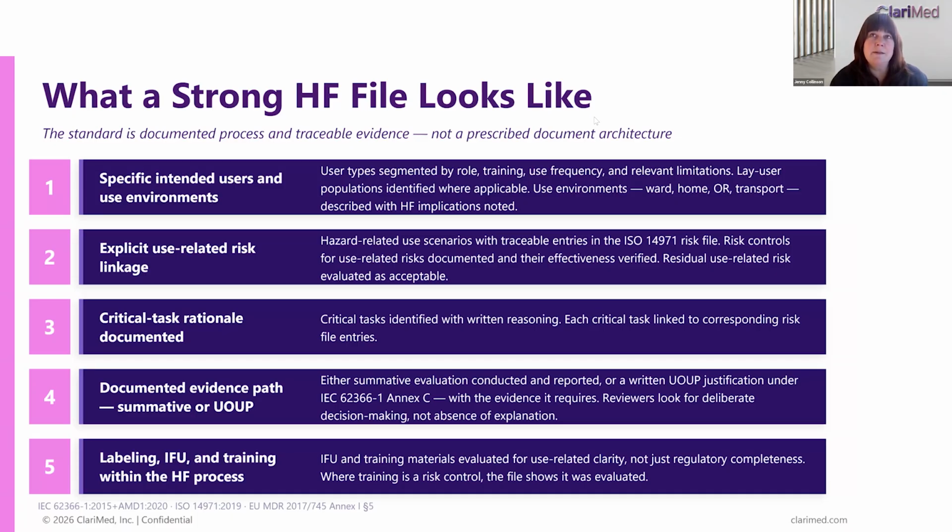Whereas if people are familiar with how they work for the FDA, that is a separate and standalone human factors file with some linkages back to a use-related risk assessment. 62366 and the MDR expect that very robust link back to 14971.